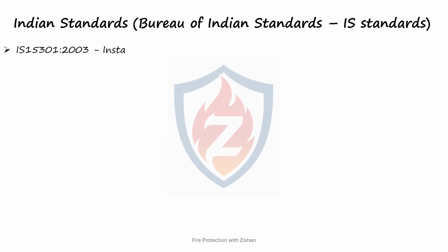Moving on to another important fire protection standard, let's discuss IS 15301:2003, which covers the requirements for the installation, operation, and maintenance of firefighting pump sets. Fire pumps are considered the heart of any fire protection system because they ensure the required water flow and pressure are available during a fire emergency.